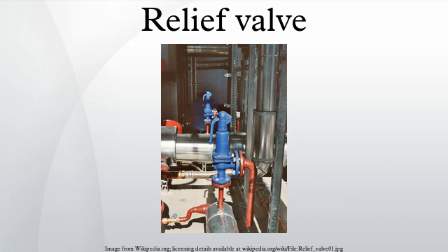For these systems often so-called differential relief valves are used. This means that the pressure is only working on an area that is much smaller than the opening's area of the valve. If the valve is open, the pressure has to decrease enormously before the valve closes, and also the outlet pressure of the valve can easily keep the valve open. Another consideration is that if other relief valves are connected to the outlet pipe system, they may open as the pressure in the exhaust pipe system increases. This may cause undesired operation.